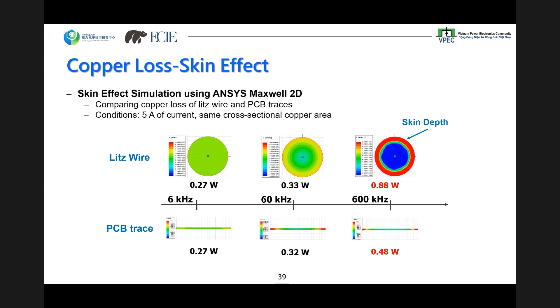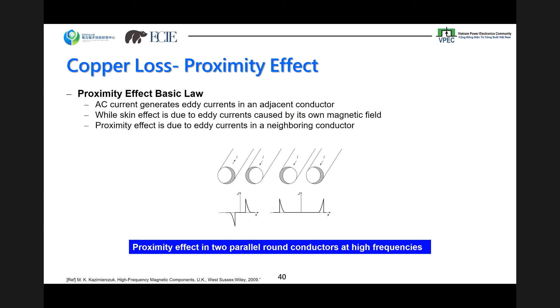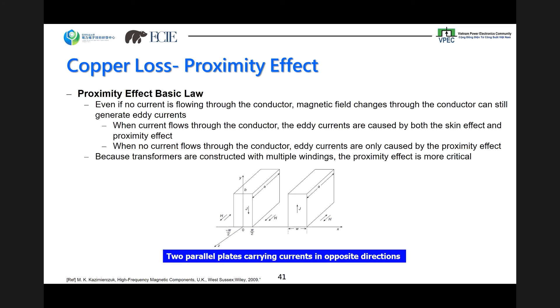This page shows the proximity effect of copper loss, and the difference between skin effect and proximity effect. Skin effect is due to eddy currents caused by its own magnetic field, but the proximity effect is due to eddy current in a neighboring conductor. So when current flows through the conductor, eddy currents are caused by both the skin effect and proximity effect. When no current flows through the conductor, eddy currents are only caused by the proximity effect. But transformers are constructed with multiple windings, so the proximity effect is more critical.